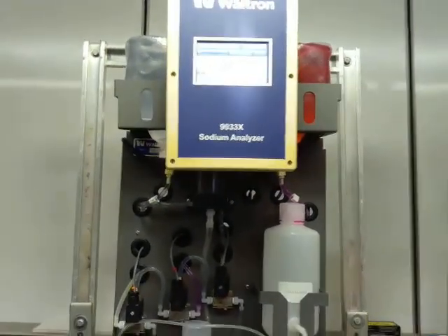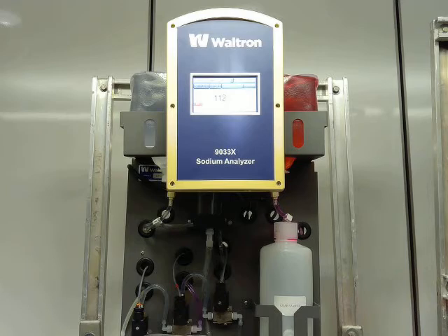One thing that I didn't mention yet when we're looking at that command screen is that there's no start button. This analyzer is in continuous operation, so once it's powered on, it assumes that you're online, you're running, and the analyzer is in normal operation. So that abort operation button isn't going to do anything unless you're in a cal or grab sample state.